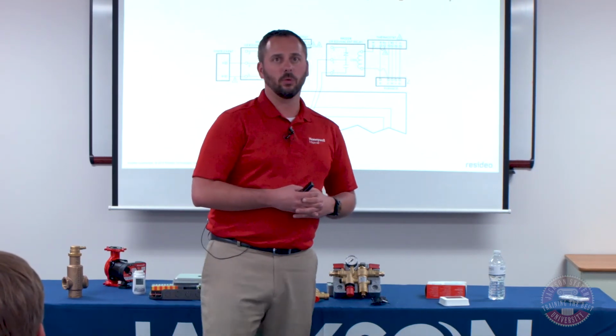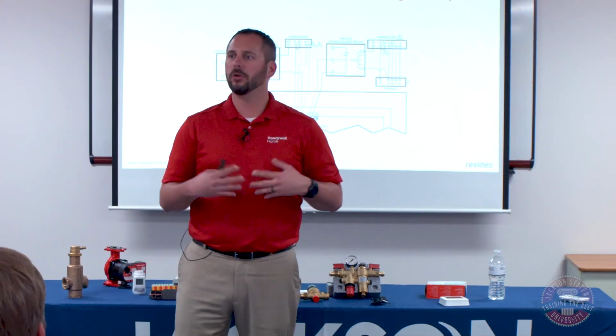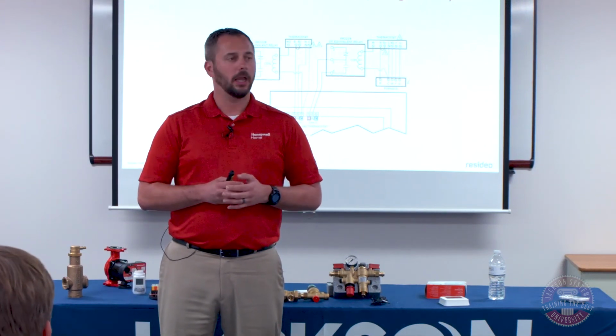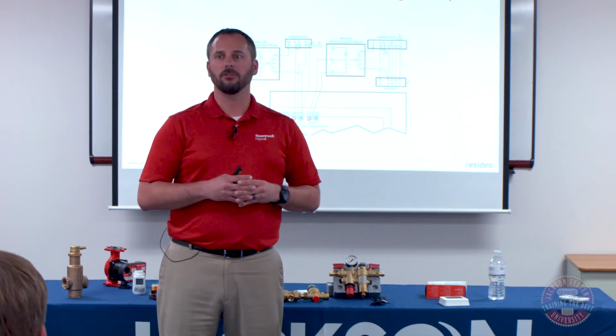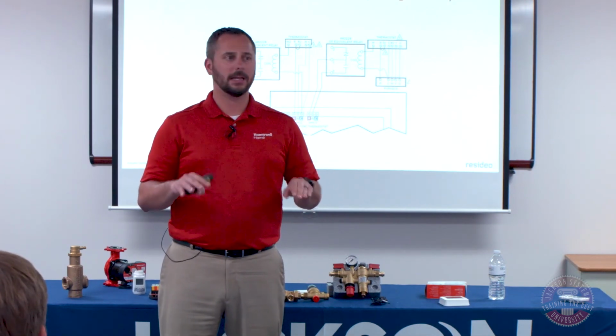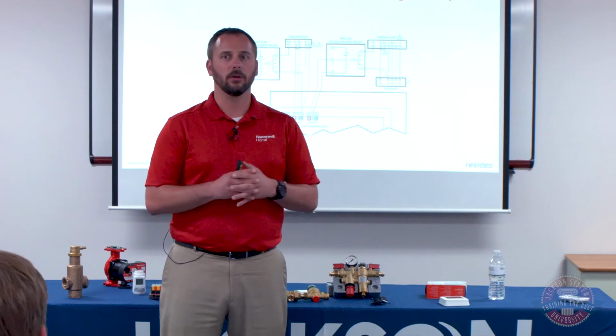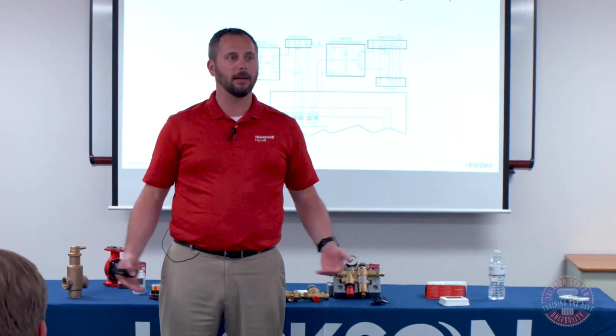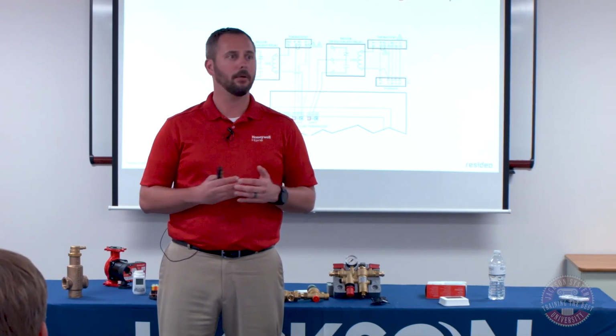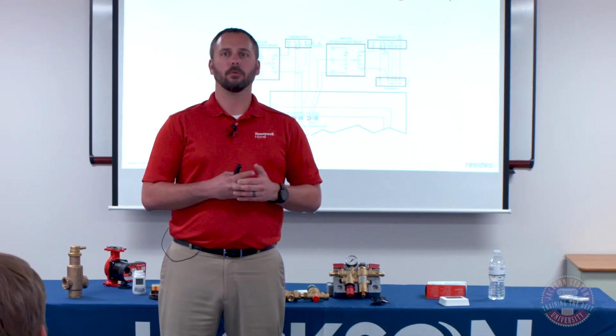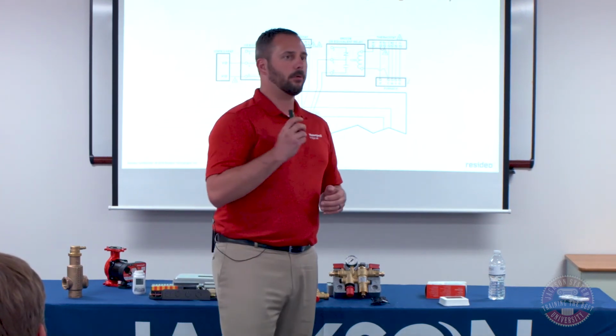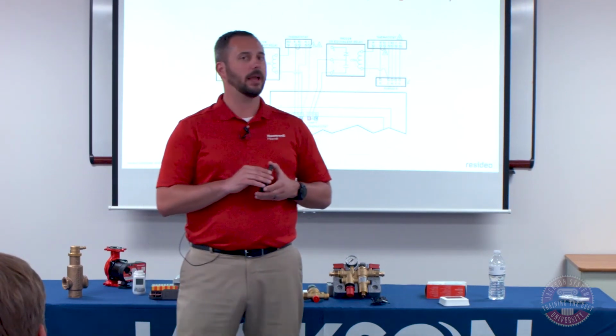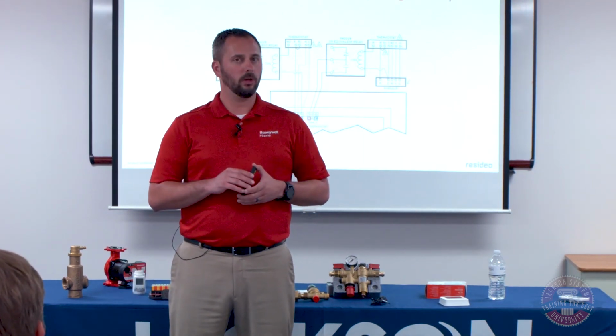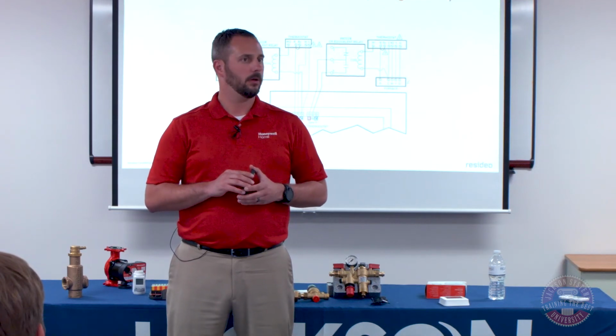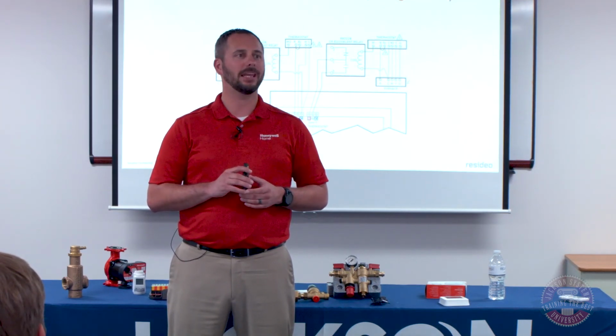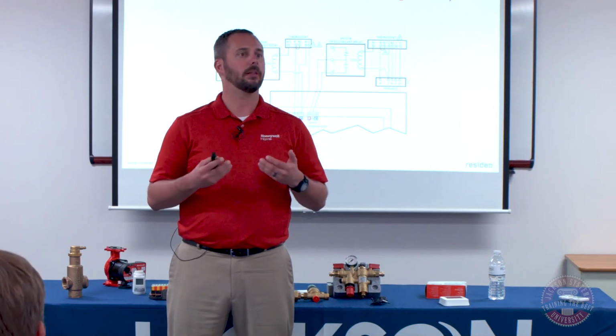One thing I will touch on is if you do get into a home where you have 2 stages of heat and you want the radiant to be first stage, if it's in-floor radiant heating, there's a lot of mass in the ground. It takes a long time to bring that mass up to temperature. I mean, if it's a slab, it could take multiple hours to bring the temperature to where you need for the thermostat. The problem with a lot of our 2-stage thermostats is it will try the radiant heating first, but even with the programming settings, a lot of times you can't give it enough time to bring that slab up.